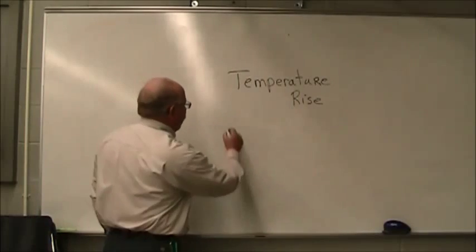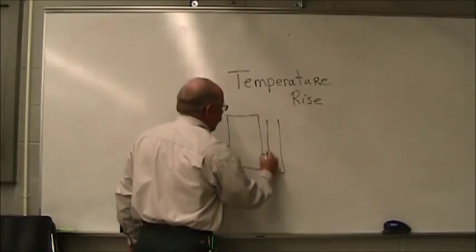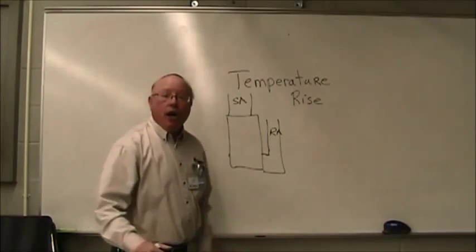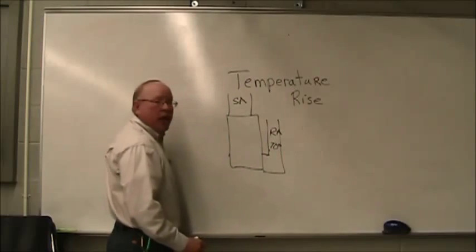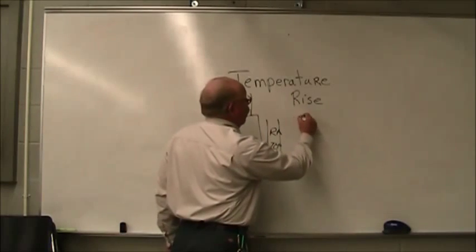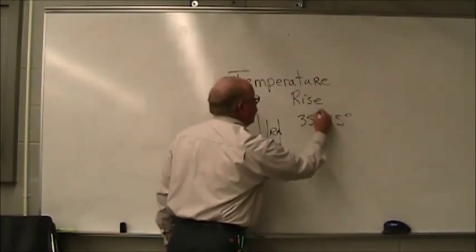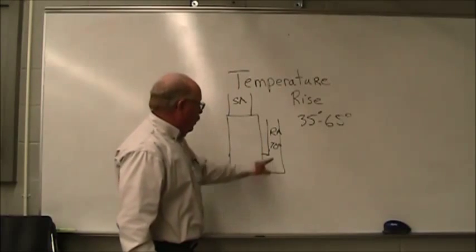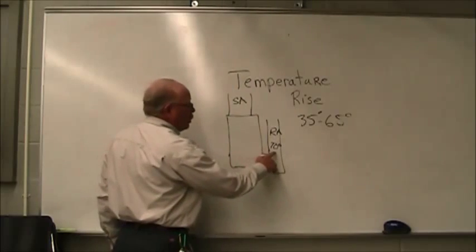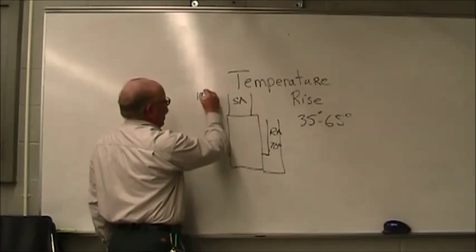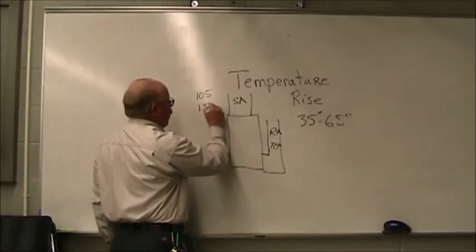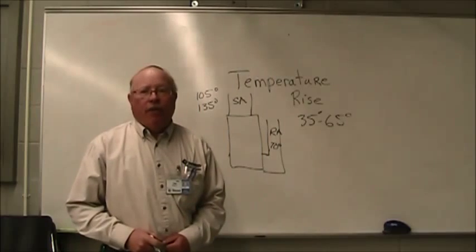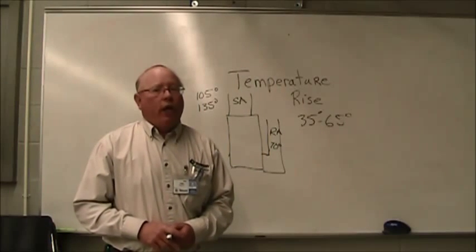So, let's say that we have a furnace here. Here's our return air — we'll call that RA — and our supply air, SA. If the return air is coming in at 70 degrees, and we have a temperature rise on our data plate of 35 to 65 degrees, then that means the air exiting out, if it's in the proper amount, should have a temperature of approximately 105 to 135 degrees Fahrenheit. If the temperature rise is too high, we're not getting enough air. If the temperature rise is too low, we're getting too much air.